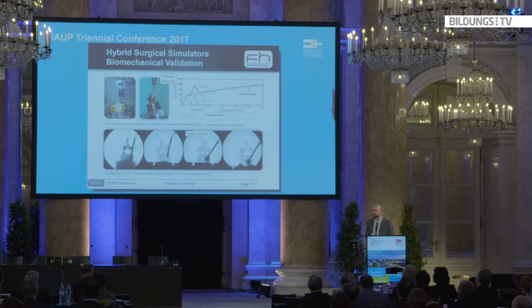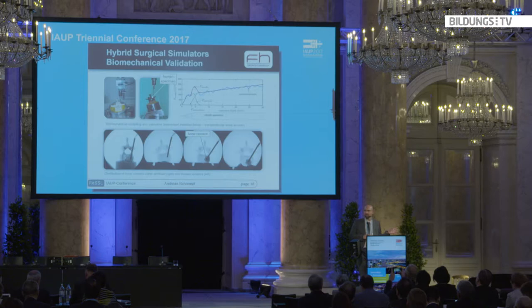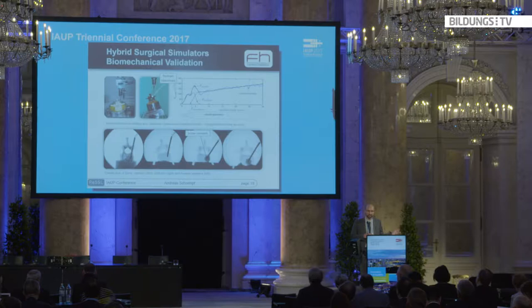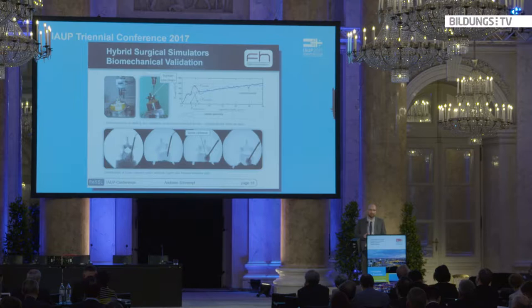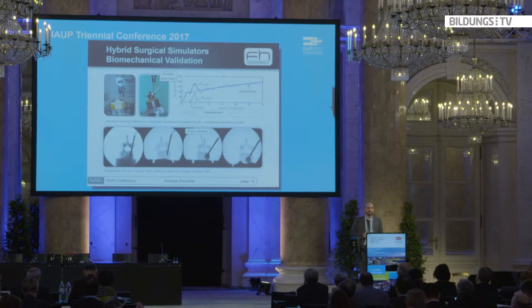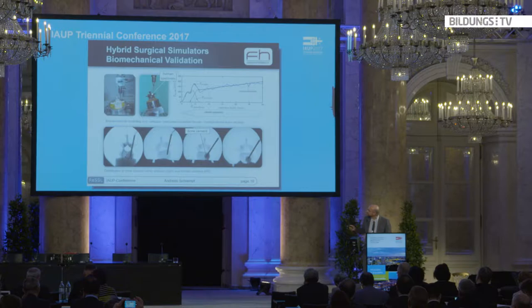Validation is a very important aspect. The first step is biomechanical validation: we have the artificial anatomy and want to know whether the haptic sensation is correct. We perform measurements with human specimens and compare whether our artificial anatomy behaves identically or very realistically. For example, we compare needle insertion into artificial vertebrae with needle insertion into a human specimen vertebra, and adjust the artificial bone to achieve good agreement.